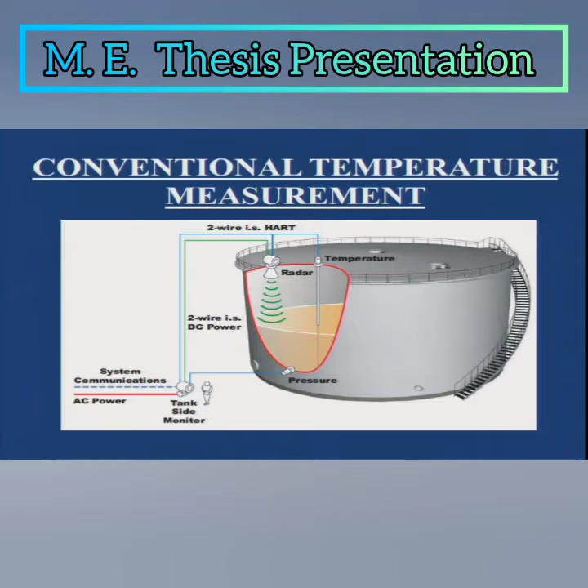In this case we are using this electrode. This electrode is going to get rusted by the fluid, and this will give an incorrect result in level measurement. Now when we talk about temperature measurement, we are using RTDs. In the case of RTDs, we insert an RTD from the top of the tank into the fluid, and the RTDs produce the temperature in the form of analog signals, and the point of the RTD is also going to be rusted by the fluid. So we are going to use a non-rusting sensor that gives the result in the form of digital signals.